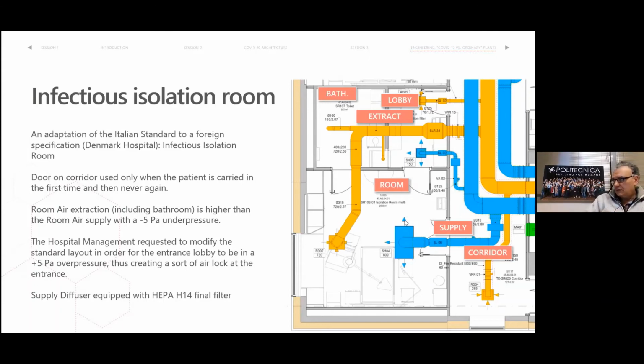So you see here there is a supply, the supply diffuser. Here there is the return extraction diffuser. So as you see, the supply is close to the door, the return is on the other side. So the bed is, let's say, washed by the clean air and then extracted.